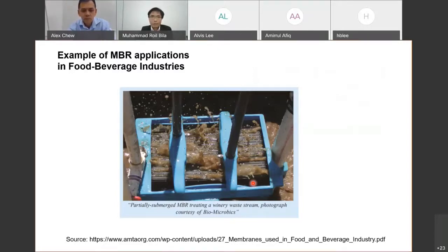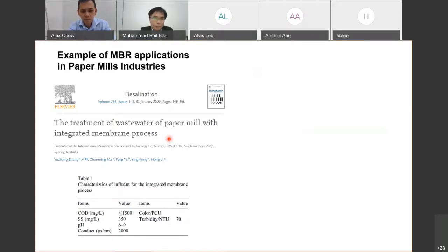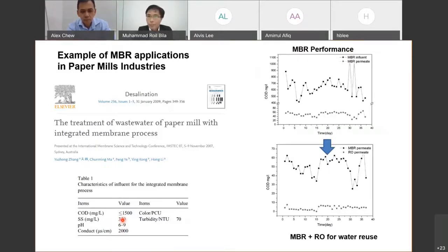I have a last example here for the pulp mill industry. We have the feed composition here. It has a very high suspended solid, 350 milligrams per liter, and the COD is quite high, up to 1500 milligrams per liter. But no worry, the MBR could reduce the COD to a level of 30 to 60 milligrams per liter.